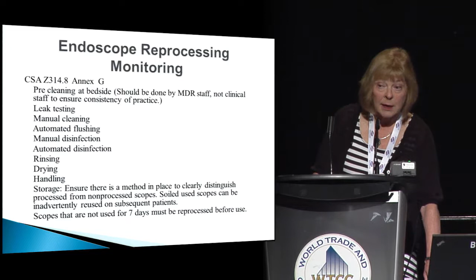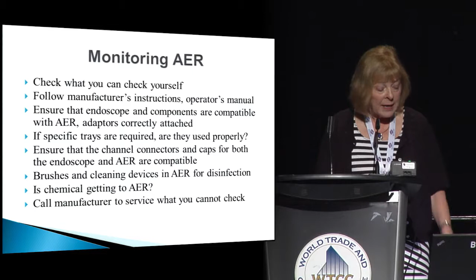Here's some of the monitoring, and it's in Annex G of .8. And the key here is for you to check what you can yourself, and what you cannot check, you call the manufacturer to check. When you are going into the MDR or wherever they are using the AERs, check the maintenance reports and make sure that the manufacturer's instructions for the maintenance of the AERs and of the scopes is being followed.